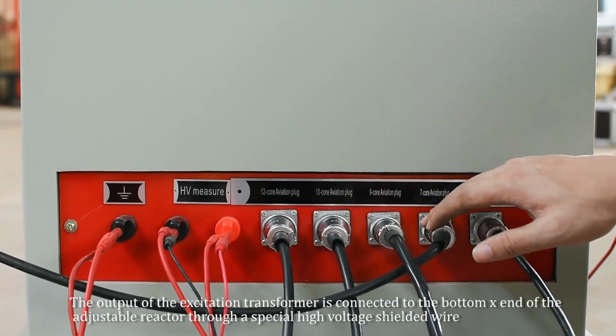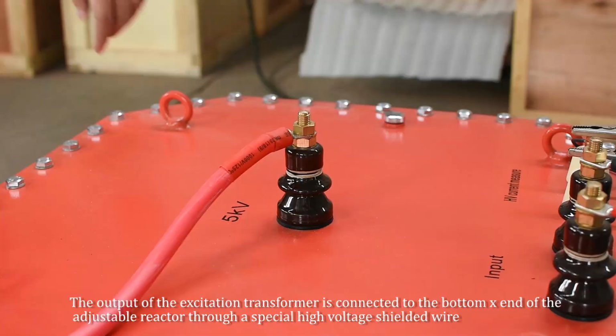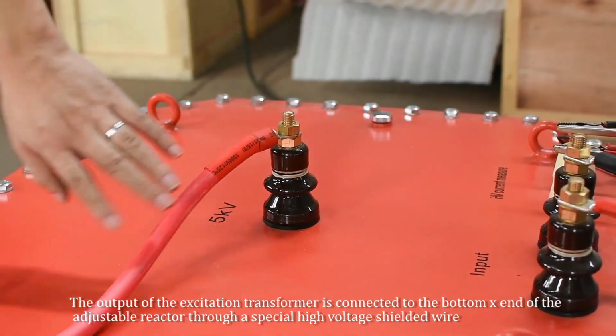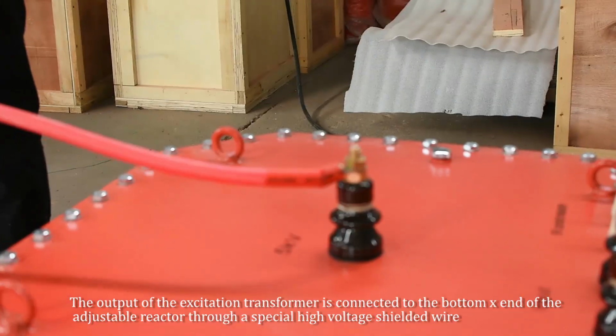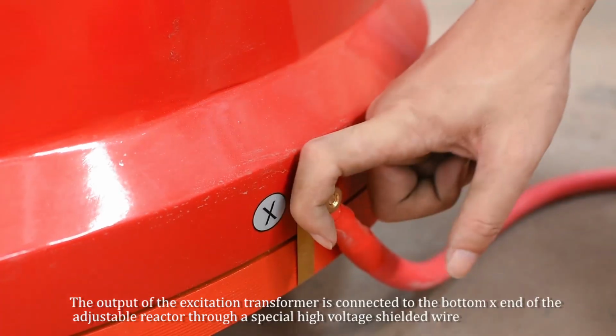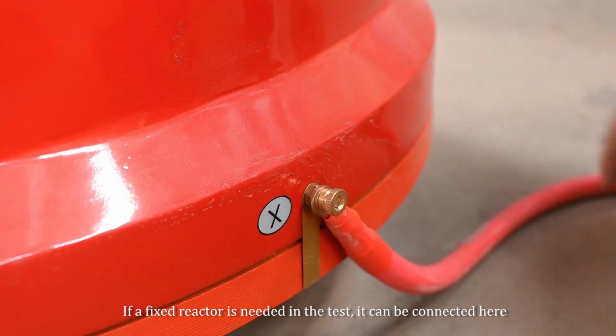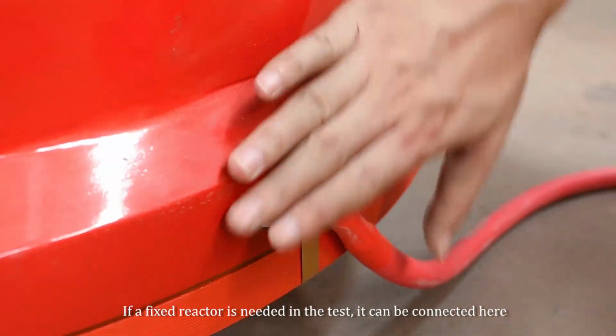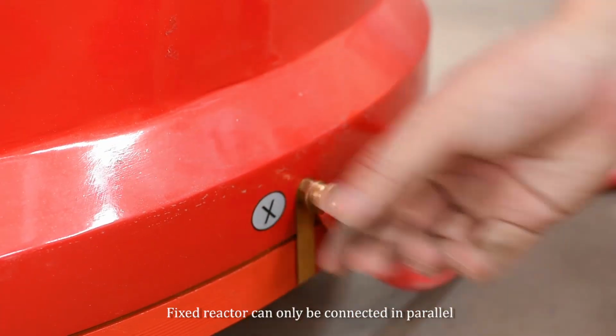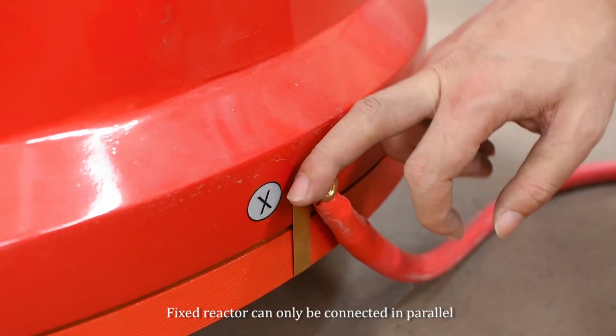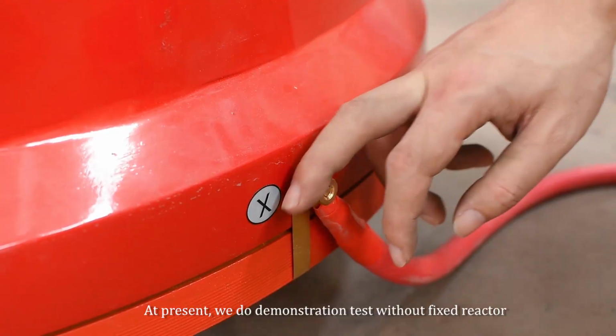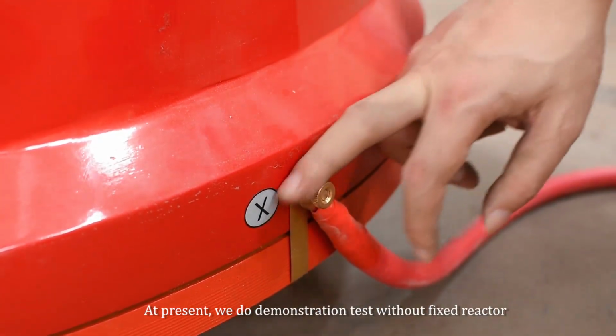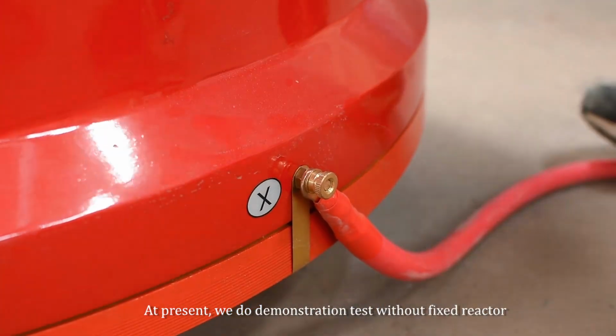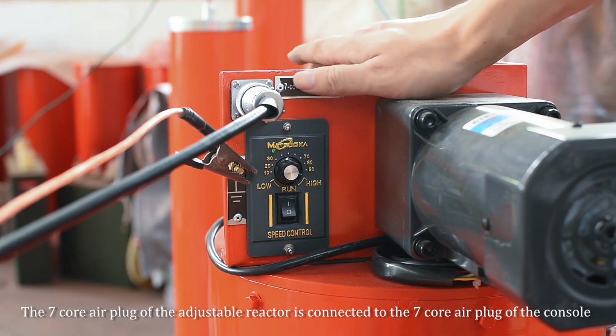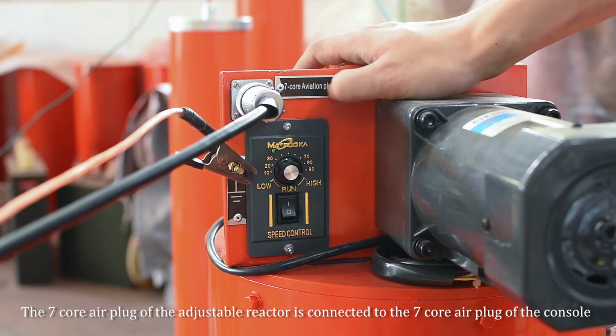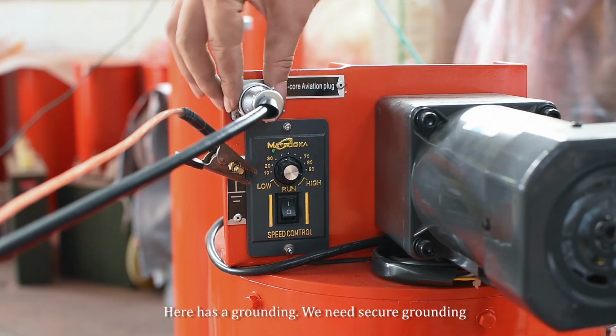The output of the excitation transformer is connected to the bottom X end of the adjustable reactor through a special high voltage shielded wire. If a fixed reactor is needed in the test, it can be connected here. Fixed reactor can only be connected in parallel. At present, we do a demonstration test without a fixed reactor. The 7-core Aviation plug of the adjustable reactor is connected to the 7-core Aviation plug of the console.